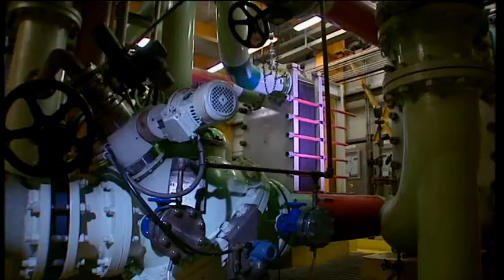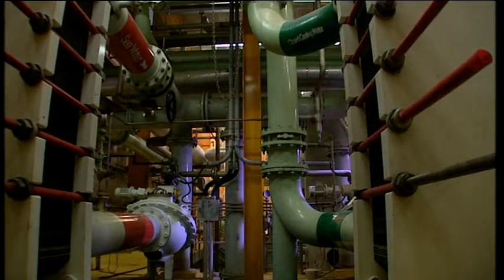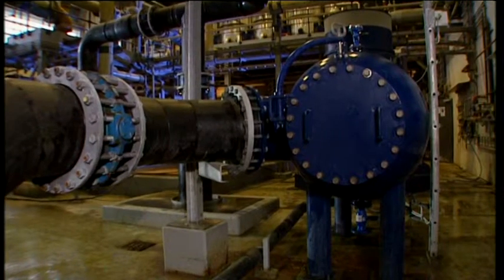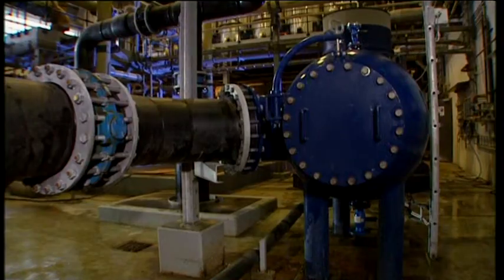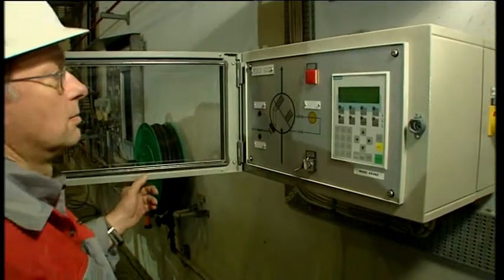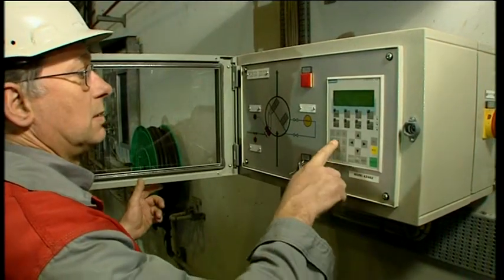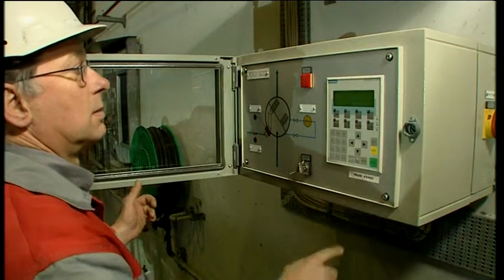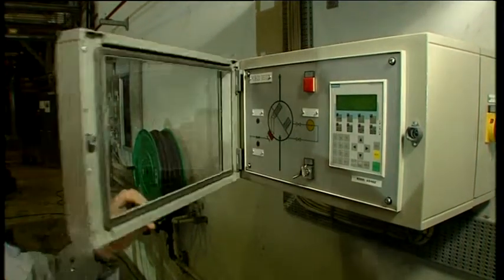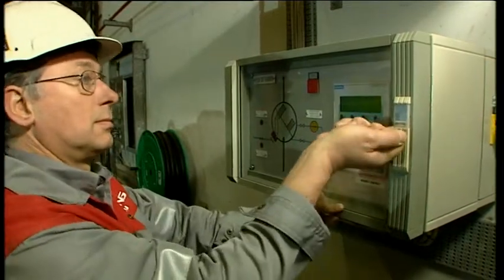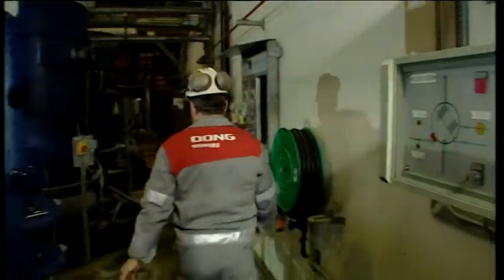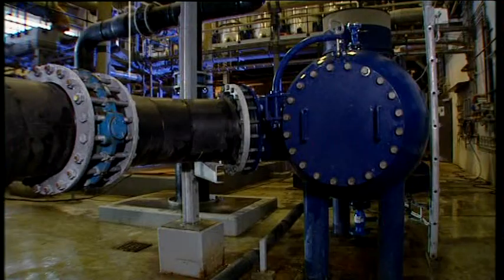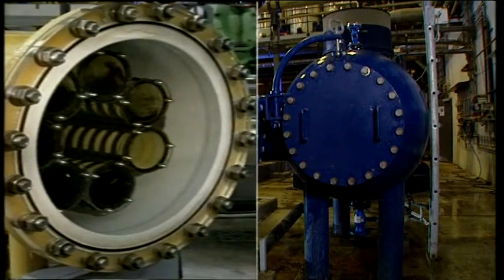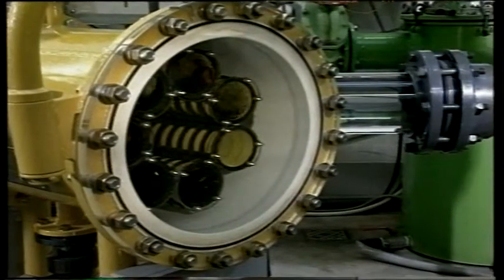With the conception of IN-TA-CT, it became more and more apparent that not only big condensers had to be protected by high-performance filters, but also the secondary and auxiliary cooling circuits. Here too, Taprogge was a driving force in further developments. Tubular and especially plate-type heat exchangers are protected by the PRBW100 high-performance filter, or, if the filtration degree has to be below 1 mm, the PRBW100FC fine filter is the right solution.